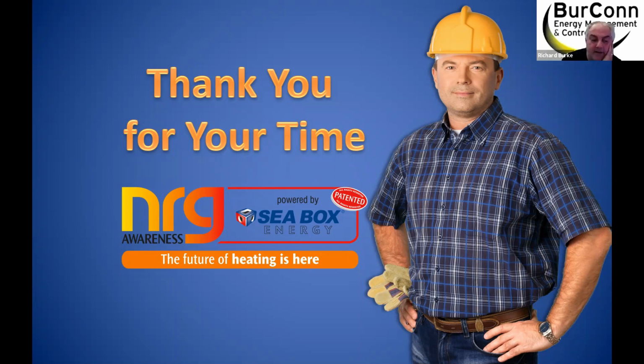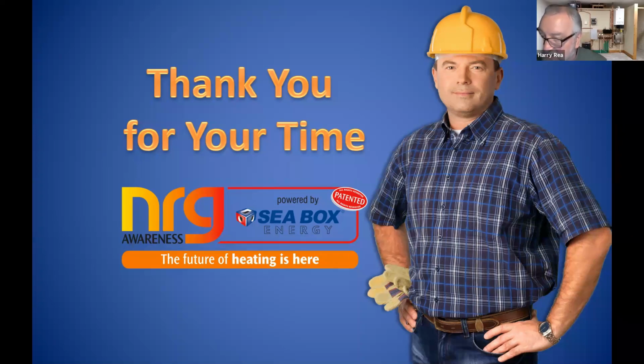I suppose, Harry, we haven't even covered the solid fuel side of it, right? We haven't. The solid fuel is really, really interesting, isn't it? I don't suppose that would be interesting for guys maybe in the southern part of England, but in Scotland and certainly in Ireland, it's extremely interesting. It's extremely versatile because remember, one of the attributes is you can have a gravity system with no pump on one side, and a fully pumped system on the other side, and they don't conflict.